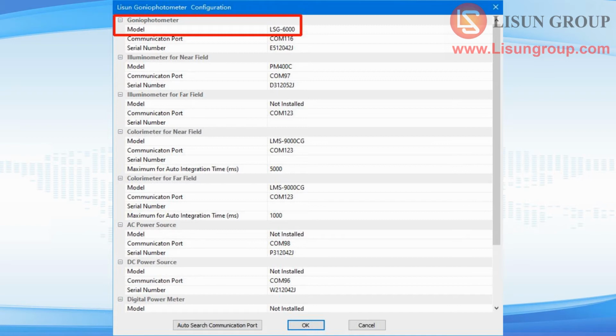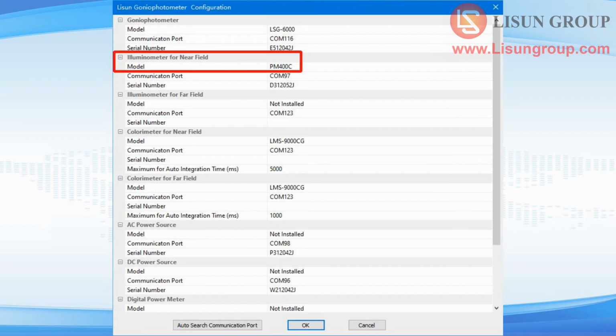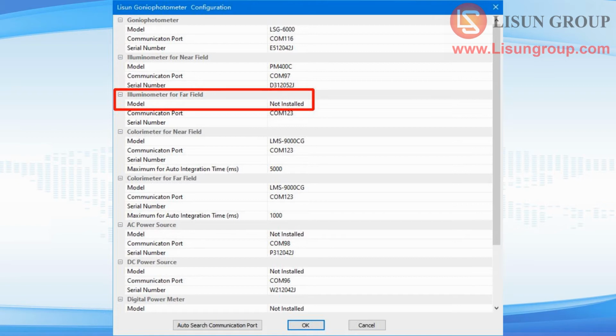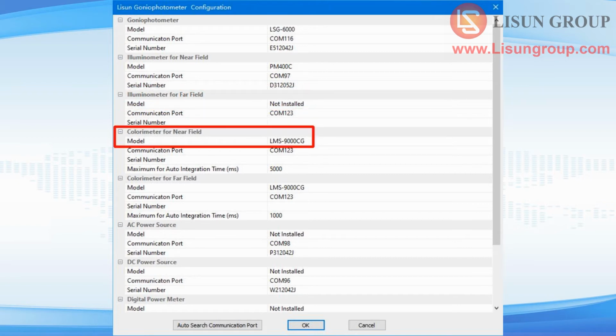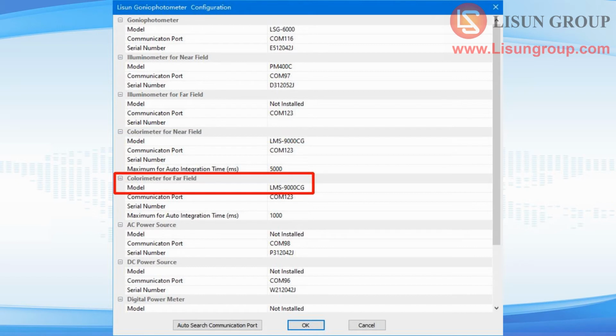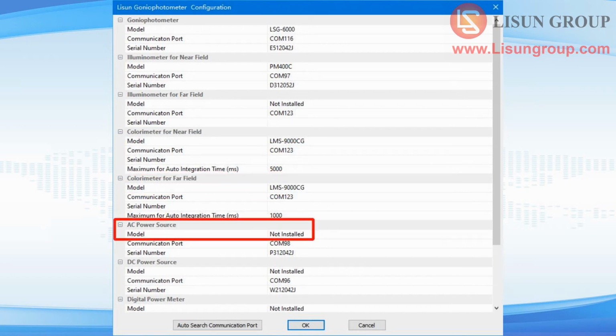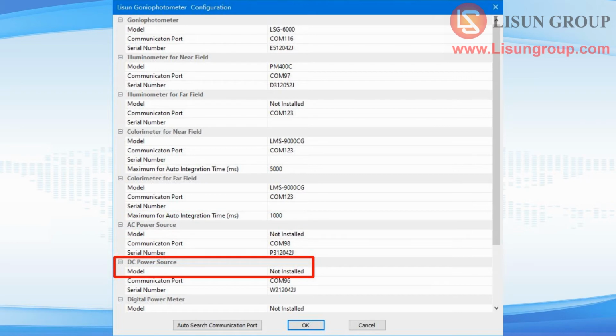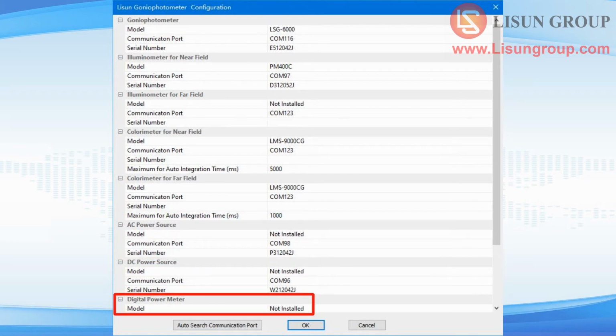The goniophotometer, the near-field photodetector, the far-field photodetector, the near-field spectroradiometer, the far-field spectroradiometer, the AC power source, the DC power source, the digital power meter. Click Auto Search Communication Port when all are selected correctly. If you only have one photodetector and one spectroradiometer in the darkroom, the default is near field. This operation video takes one photodetector and one spectroradiometer as an example.